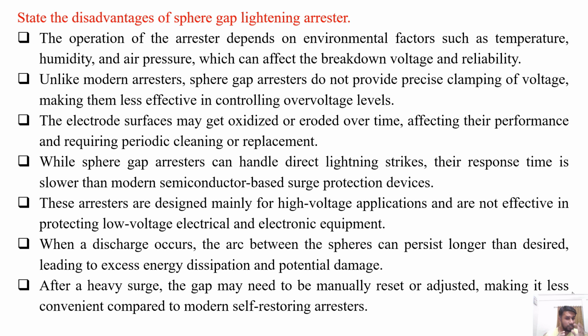replacement. While sphere gap arresters can handle direct lightning strikes, their response time is slower than modern semiconductor-based surge protection devices. These arresters are designed mainly for high voltage applications and are not effective in protecting low voltage electrical and electronic components or equipment. When a discharge occurs, the arc between the spheres can persist longer than desired, leading to excess energy dissipation and potential damage to the arrestor.